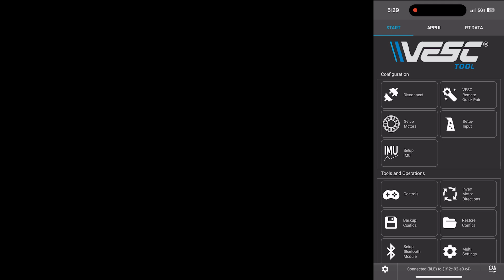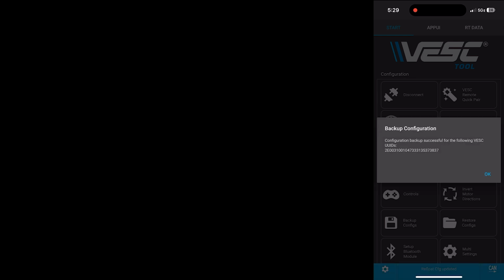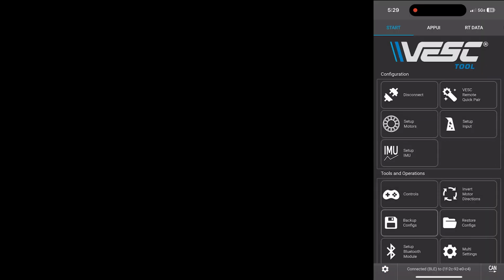There's the backup configs button at the bottom of the main screen. This is what we want to hit after making sure we're connected to the actual controller, the ADV500. We hit that button, then OK, and that's it. Now we can restore it if we screw something up. But once we've made all our changes and tested them, you probably want to make a fresh backup overriding the previous one, so you have all those fixes in the backup as well.